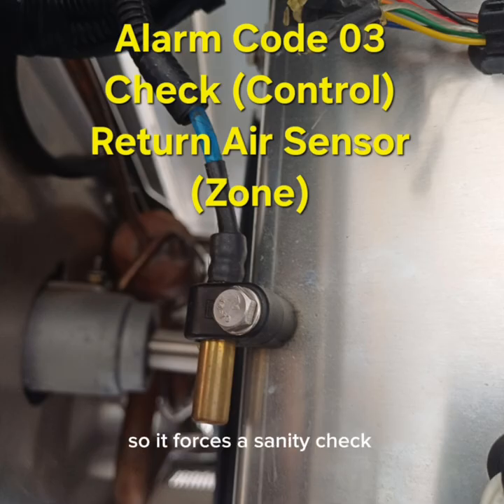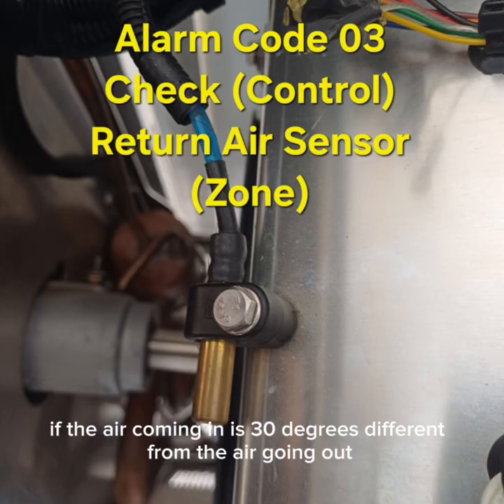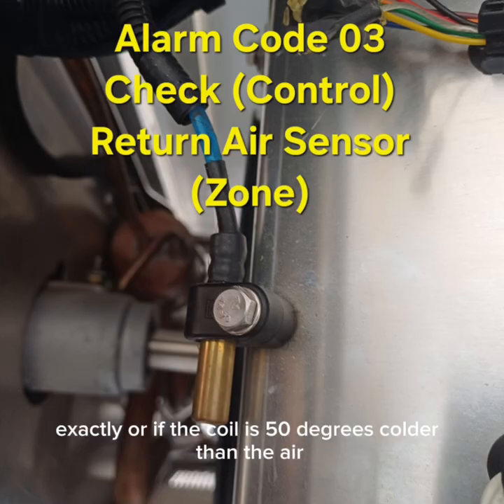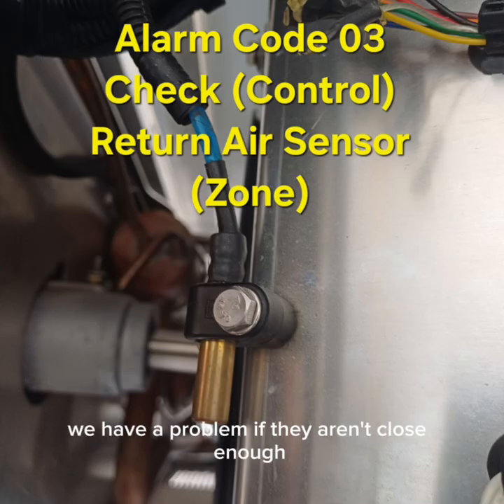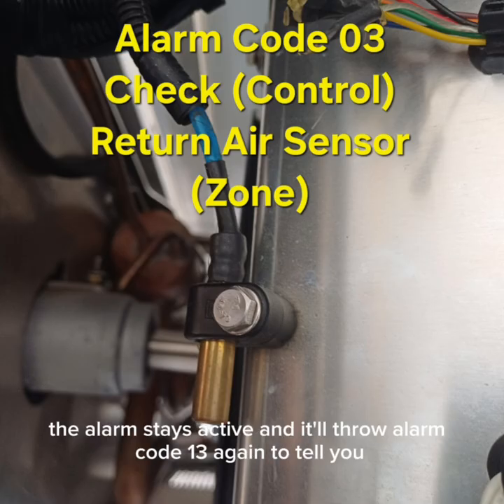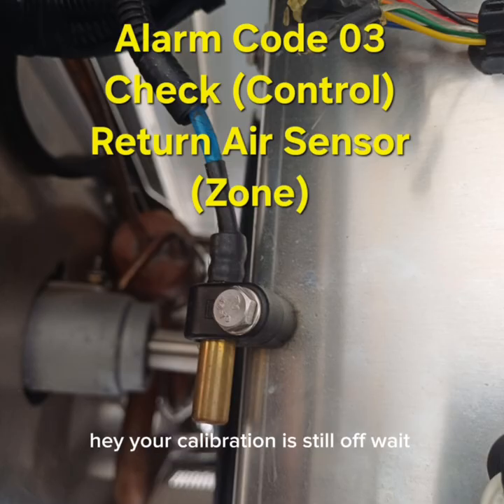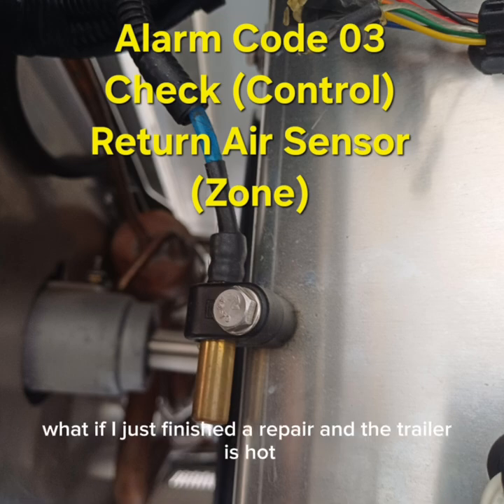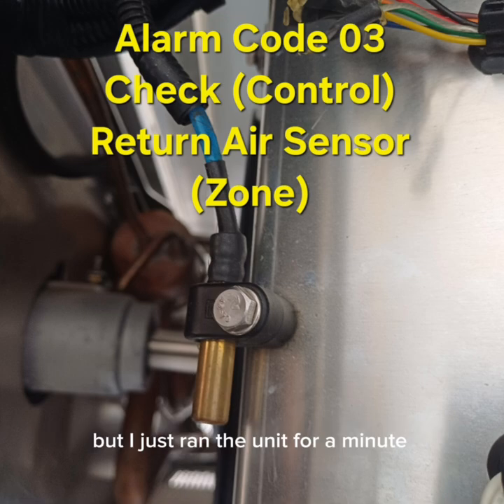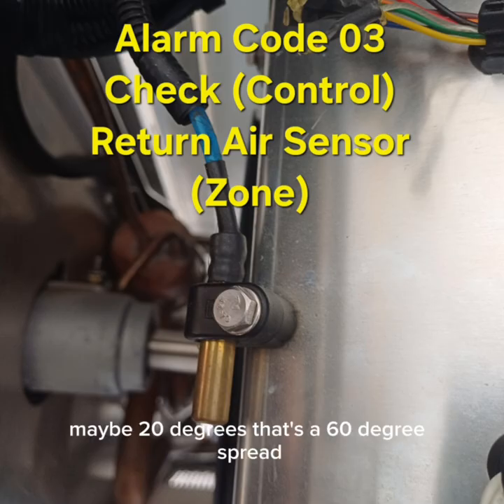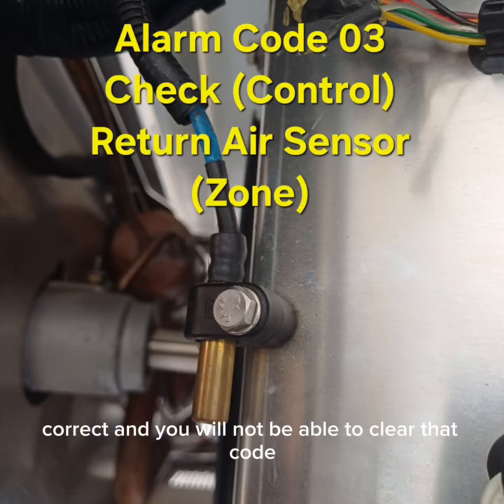Wow. So it forces a sanity check. It's basically saying if the air coming in is 30 degrees different from the air going out, something is physically wrong. Exactly. Or if the coil is 50 degrees colder than the air, we have a problem. If they aren't close enough, the alarm stays active and it'll throw alarm code 13 again to tell you, hey, your calibration is still off. Wait, play this out for me. What if I just finished a repair and the trailer is hot, say it's 80 degrees inside, but I just ran the unit for a minute so the coil is now freezing cold, maybe 20 degrees? That's a 60-degree spread. Correct, and you will not be able to clear that code.